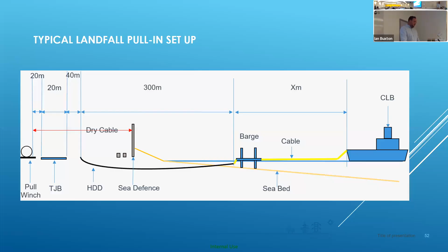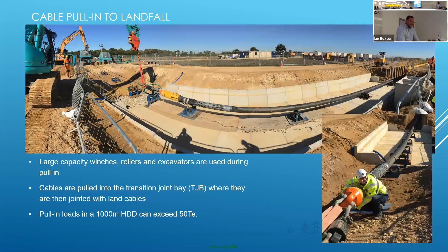Here's the East Anglia 1 cable - I think it was a 1200 meter pull-in, and we saw tension on this cable in excess of 50 tons during pull-in. In the very distance here is the Maersk connector, the vessel I showed you that beached - maybe 1200 meters away - and that cable is connected to the Maersk connector, being pulled into our transition joint bay. Here's a very happy cable design engineer to show you the size of this cable that's pulled in - a successful operation.